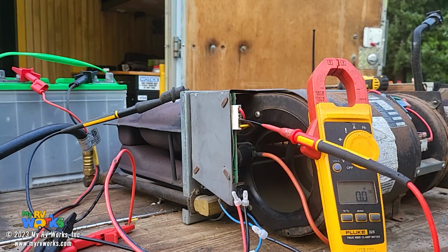Because I've tried 3 times, I couldn't. I waited an hour, I tried 3 more times, I couldn't. Therefore, I'm never going to try again, and we call that hard lockout. All you have to do to clear any of these lockout conditions is turn off your call for heat and turn your call for heat back on again, and it will start. Now what's happening is this furnace will run forever as long as the thermostat is calling for heat. Now why is it going to do that?